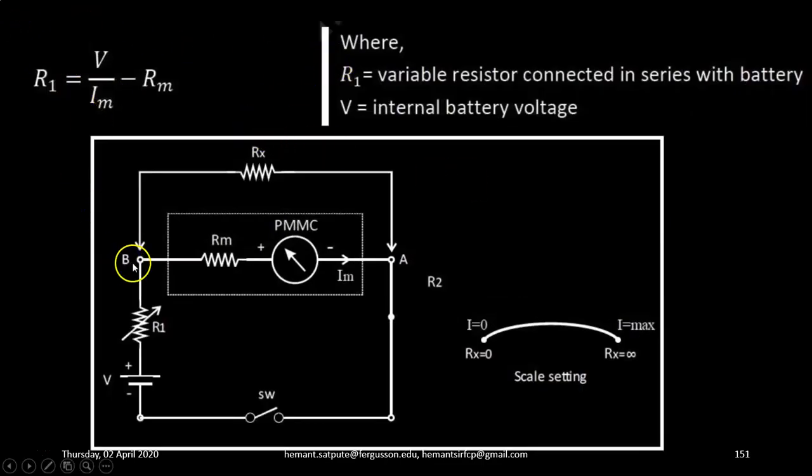The value of this resistance R1 can be calculated by using the formula R1 equals V upon Im minus Rm, where R1 is the variable resistor connected in series with the battery, V is the internal battery voltage, Rm is the meter resistance, and Im is the maximum full scale deflection current which the meter can take.